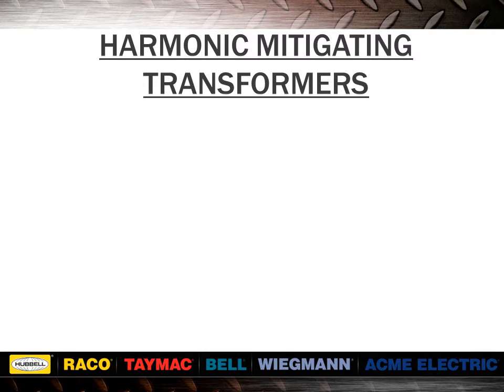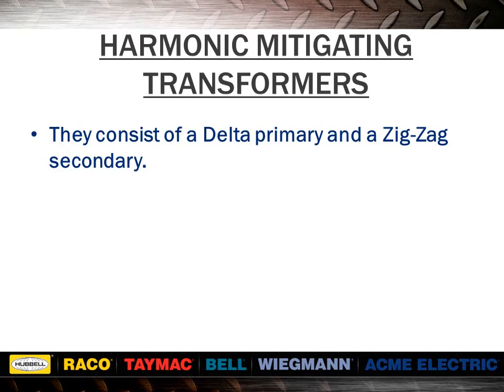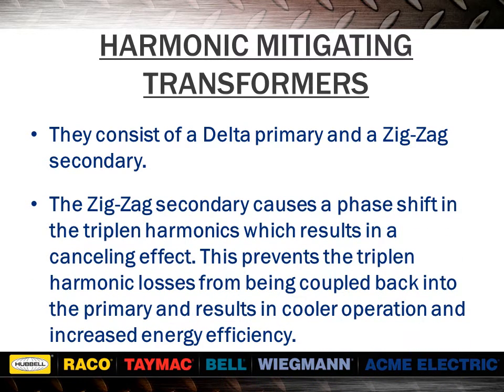Next, we will discuss harmonic mitigating transformers. They consist of a delta primary and a zigzag secondary. The zigzag secondary causes a phase shift in the triplen harmonics, which results in a canceling effect. This prevents the triplen harmonic losses from being coupled back into the primary and results in cooler operation and increased energy efficiency.